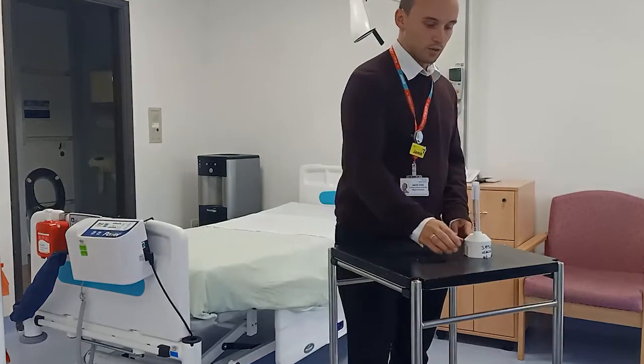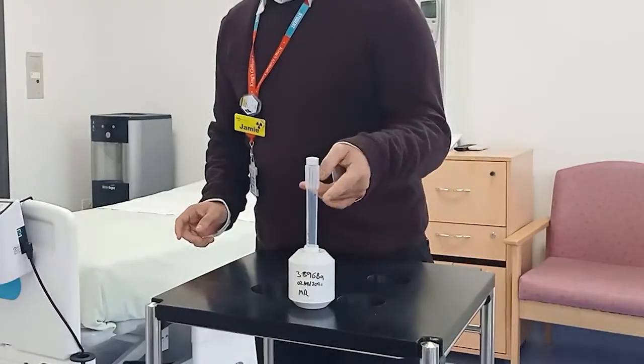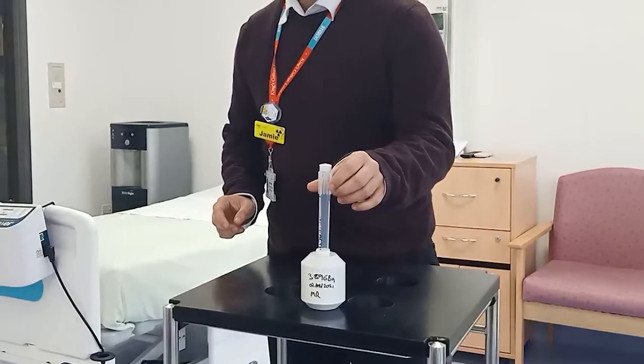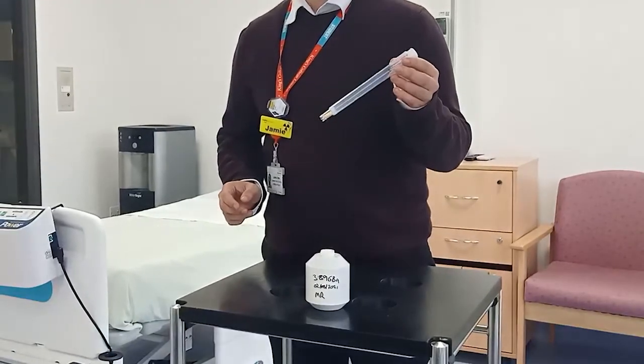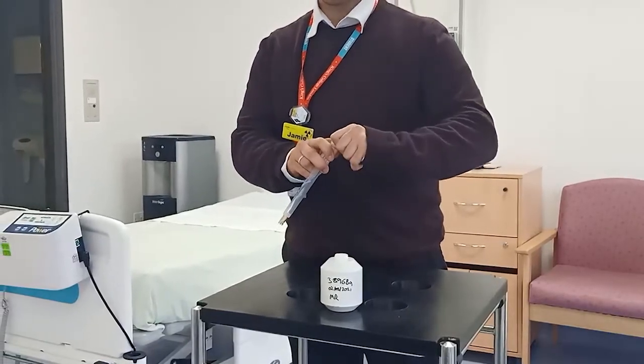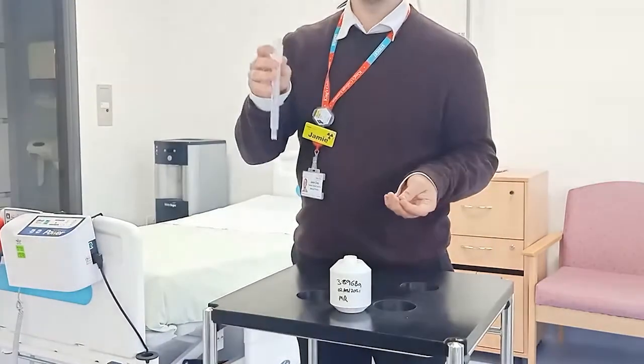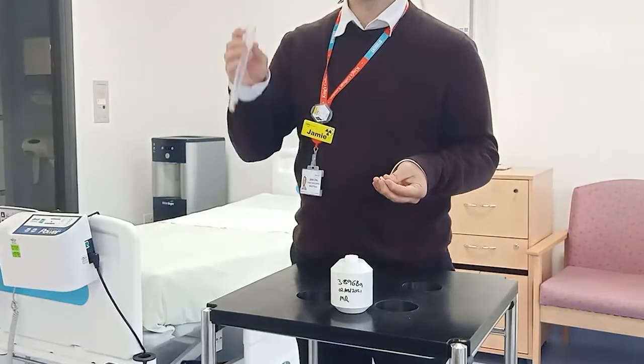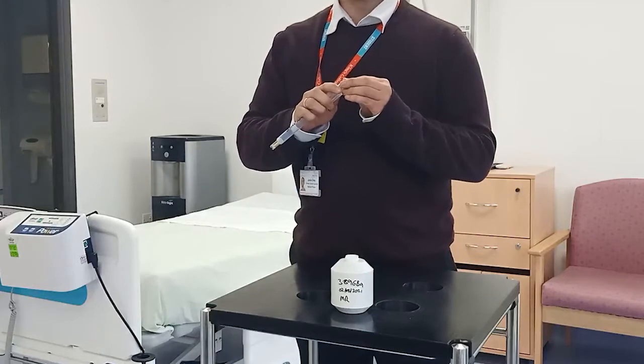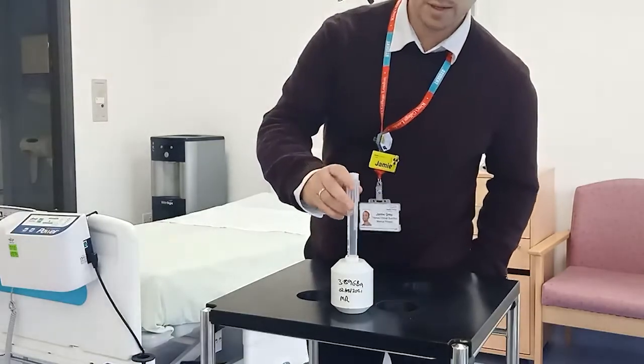This is the pot that the thyroid capsule is given in. This tube serves three purposes: it means the patient doesn't have to directly touch the capsule since it's so radioactive; there's an opening at the top where the capsule comes out so they can wrap their mouth around the tube and take it back; it also means they can't drop the capsule, which is a big consideration; and it keeps things sterile so no one has to touch it while they're taking it.